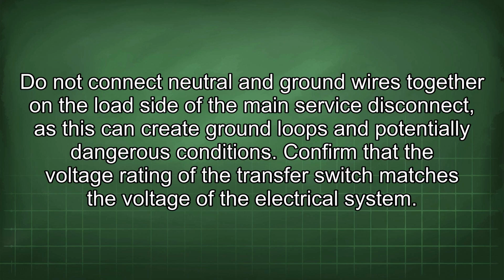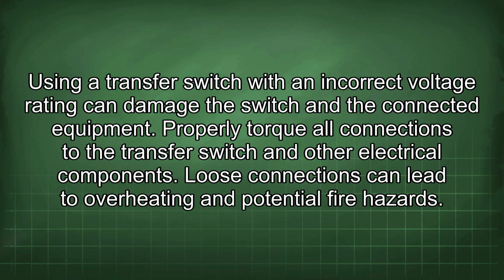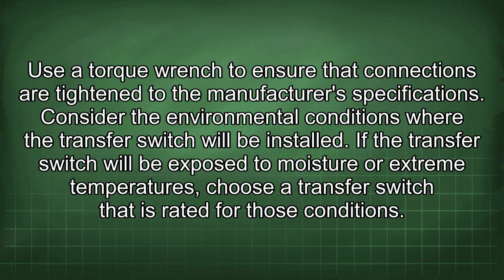Confirm that the voltage rating of the transfer switch matches the voltage of the electrical system. Using a transfer switch with an incorrect voltage rating can damage the switch and the connected equipment. Properly torque all connections to the transfer switch and other electrical components. Loose connections can lead to overheating and potential fire hazards. Use a torque wrench to ensure that connections are tightened to the manufacturer's specifications.